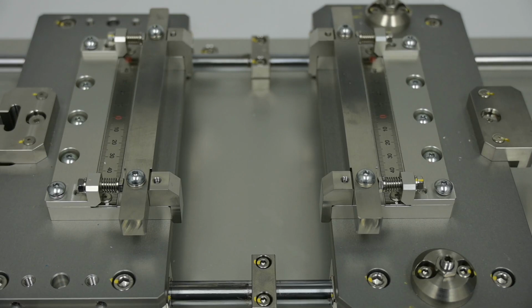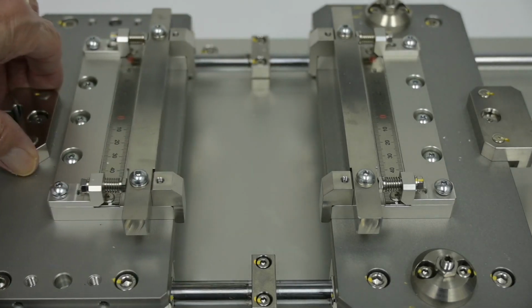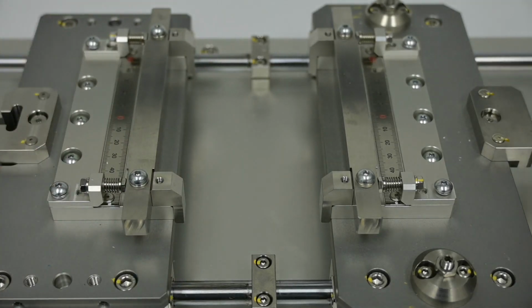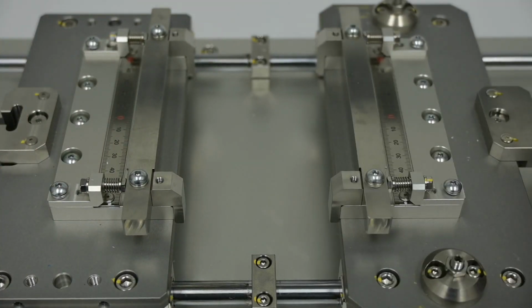Now I will install the load cell clamp on an FS-N in my case. The ST would be the same. This is the fixed clamp. This is the moving clamp. It moves back and forth with the motor. The fixed clamp can move back and forth, but it gets locked down during tests with 2 knurled nuts, one on each side of the locking point.